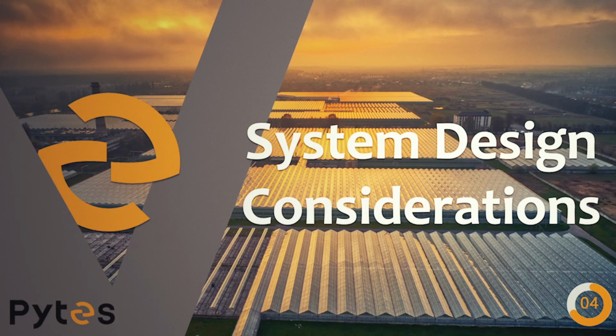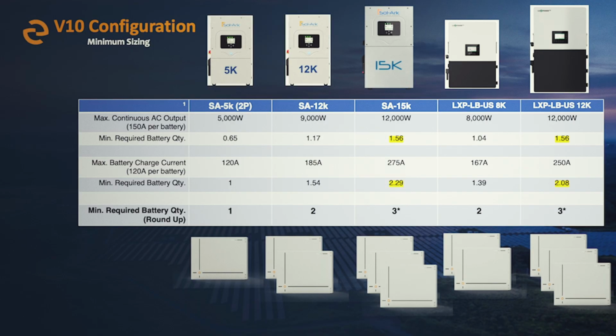Just a couple things on minimum sizing. This is for V10 specifically, but you can also do it with V5 and the other models. Looking at your inverter maximum AC output, how many batteries do we need to satisfy that? You also want to look at your inverter max charge rate, how many batteries do we need to accept that? And always round up, right? It's never a problem to have more. But what's interesting is some of these examples, just really simple math. You can see we need 2 batteries to hit our 12 kilowatts for our Solar 15K with V10. But we need 3 batteries technically to accept that 275 amp charge rate.